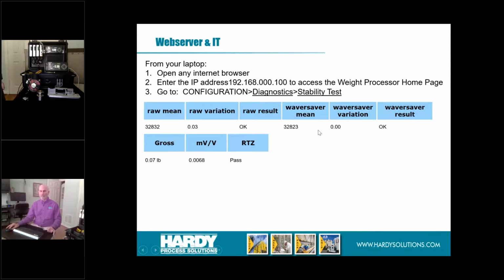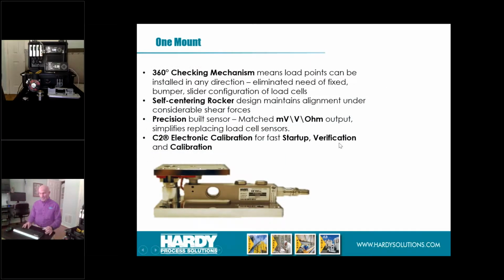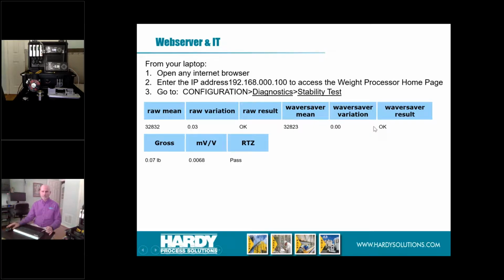So what does this mean for you? Let's say that you're sitting in your office, and one of your engineers out in the plant says, "We're having trouble with this scale." You ask, "Is WAVERSAVER on?" They say, "Yes, we've got it on." You pull this up and you determine that, well, you've got it on, but you don't have it fine-tuned. It's still not passing the WAVERSAVER result. So then you can go in from your office, tweak the WAVERSAVER, either the frequency or the number of averages, and then check the response just by having them add weight, take away weight, and then make sure that that's working for you. Other thing that we have over here is the gross weight that's on the scale, as well as the millivolt per volt.